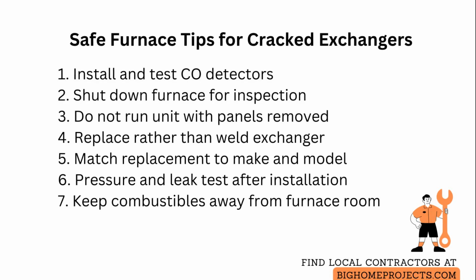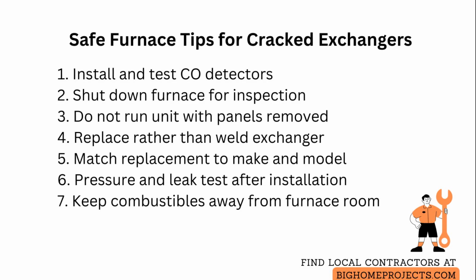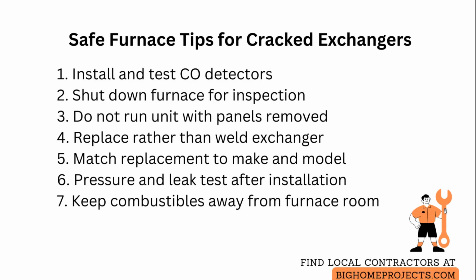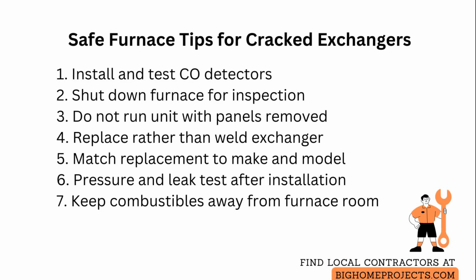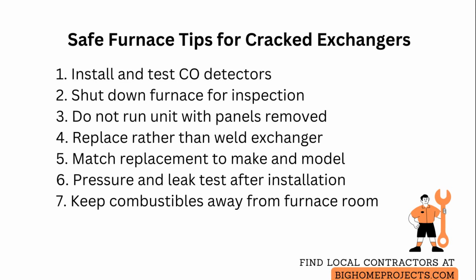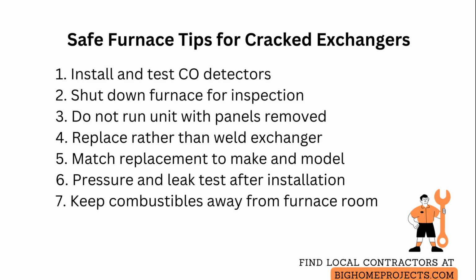Cracks also allow combustion gases and soot to circulate and corrode adjacent components, so have the furnace shut down and inspected as soon as you suspect a problem rather than waiting for intermittent symptoms. Heat exchanger failure can create hot spots and flame rollout that increase the risk of an ignition in the burner compartment. So do not attempt temporary bypasses or run the unit with service panels removed.